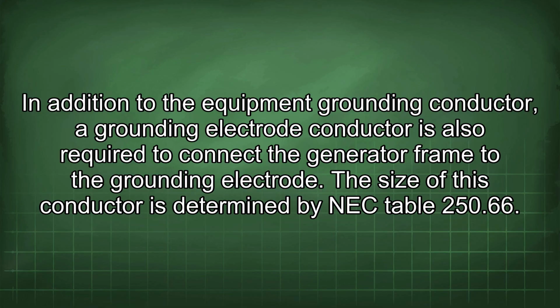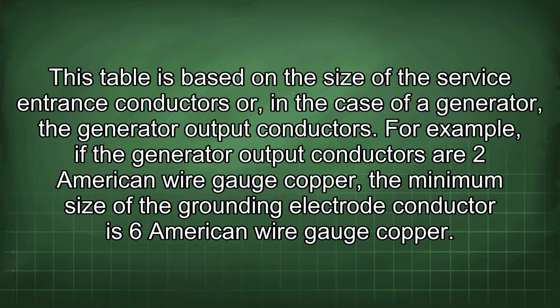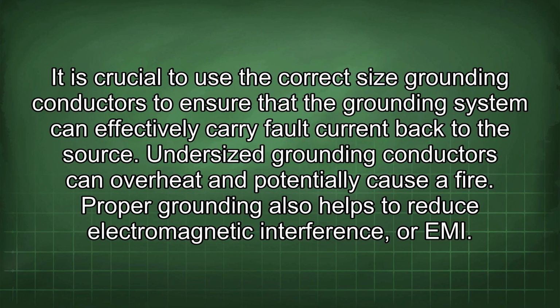The size of this conductor is determined by NEC Table 250.66. This table is based on the size of the service entrance conductors or, in the case of a generator, the generator output conductors. For example, if the generator output conductors are 2 American wire gauge copper, the minimum size of the grounding electrode conductor is 6 American wire gauge copper. It is crucial to use the correct size grounding conductors to ensure that the grounding system can effectively carry fault current back to the source.